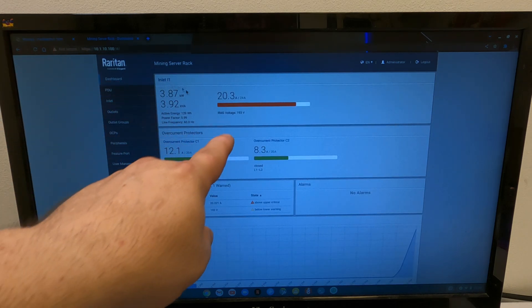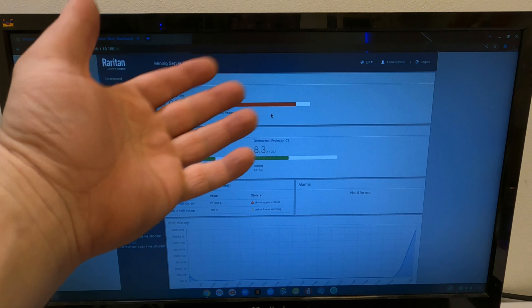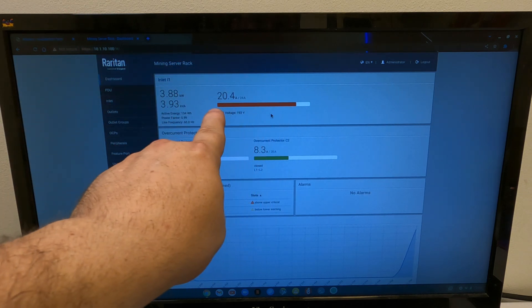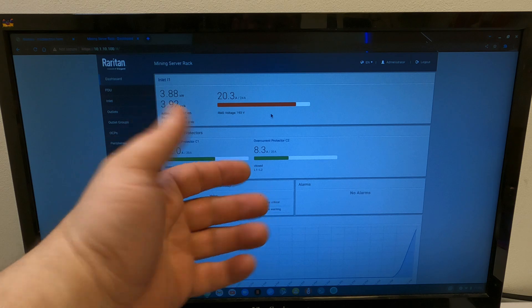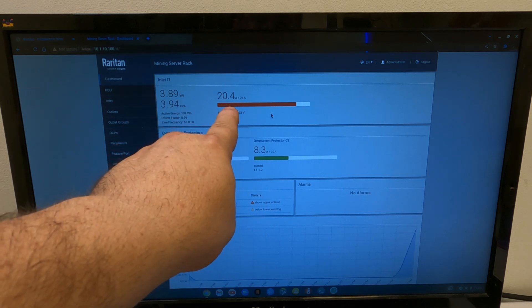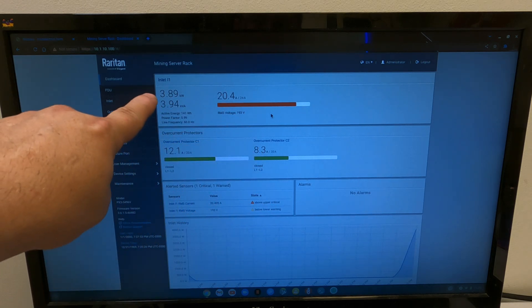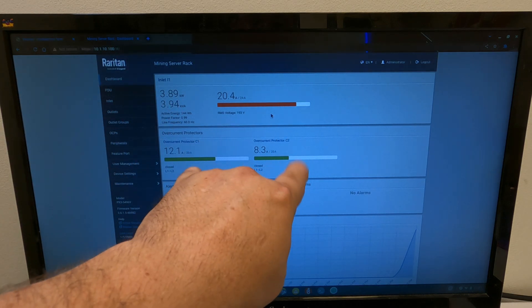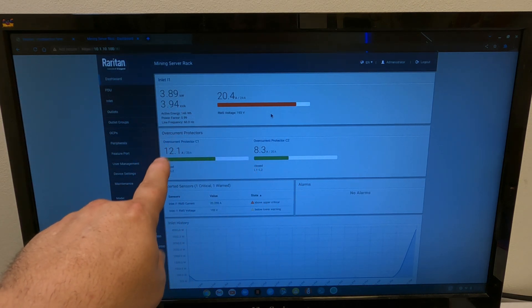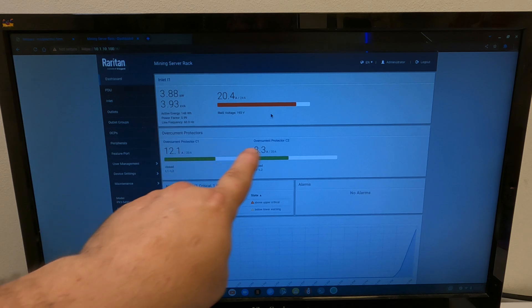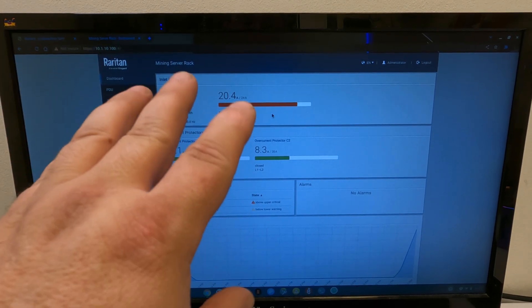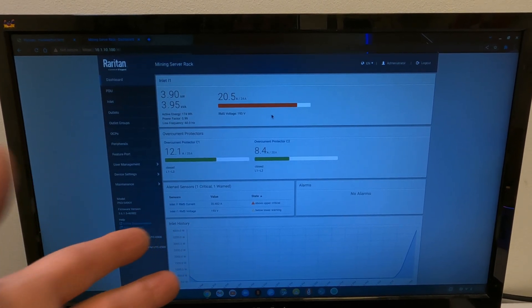Nice. Okay, RMS voltage. I do have some voltage drop on this line, unfortunately. That's why it's red. And we're running a little low. We are pulling 20.4 amps right now, 3.88 kilowatts. And we can see on each half here, this one's pulling 12.1 amps and this one's pulling 8.3 amps. Gives you all the information. Now, let's go on over to the PDU and take a look at that.